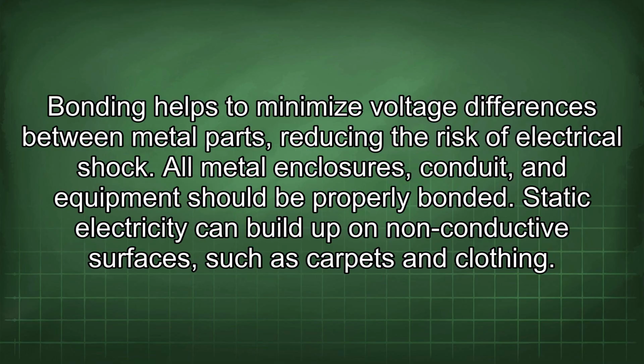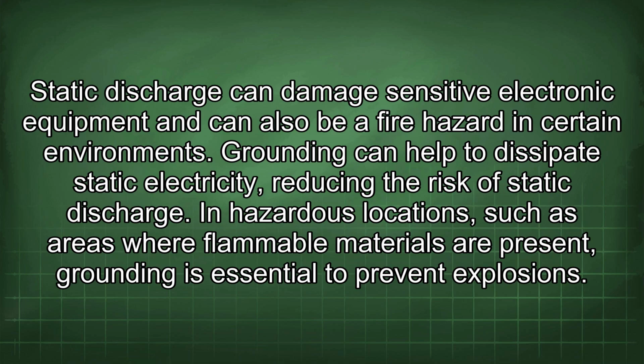All metal enclosures, conduit, and equipment should be properly bonded. Static electricity can build up on non-conductive surfaces, such as carpets and clothing. Static discharge can damage sensitive electronic equipment and can also be a fire hazard in certain environments. Grounding can help to dissipate static electricity, reducing the risk of static discharge.